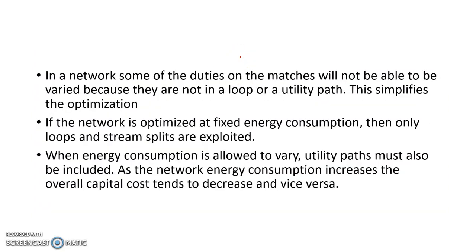Some exchanger duties cannot be varied because they are not in any loop or utility path, simplifying the optimization. If the network is optimized at a fixed energy consumption, only loops and stream splits are exploited — utility paths are not touched since using them would increase utility usage. When energy consumption is allowed to vary, utility paths must also be included, because as network energy consumption increases, the overall capital cost tends to decrease.